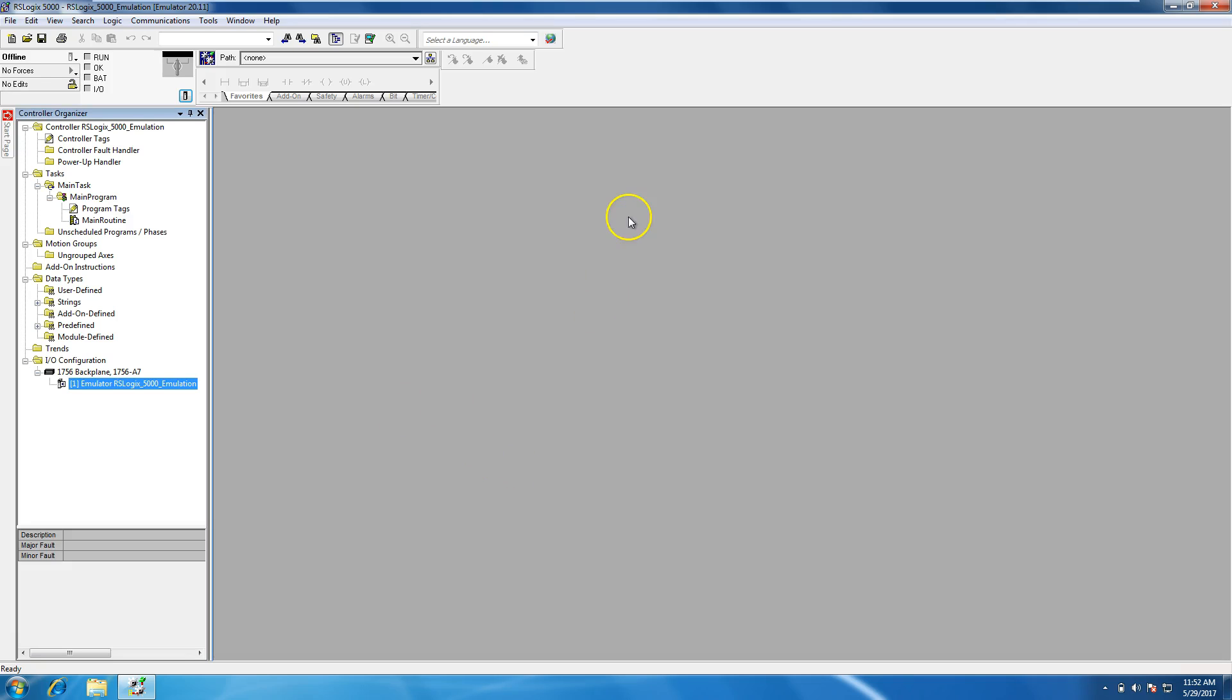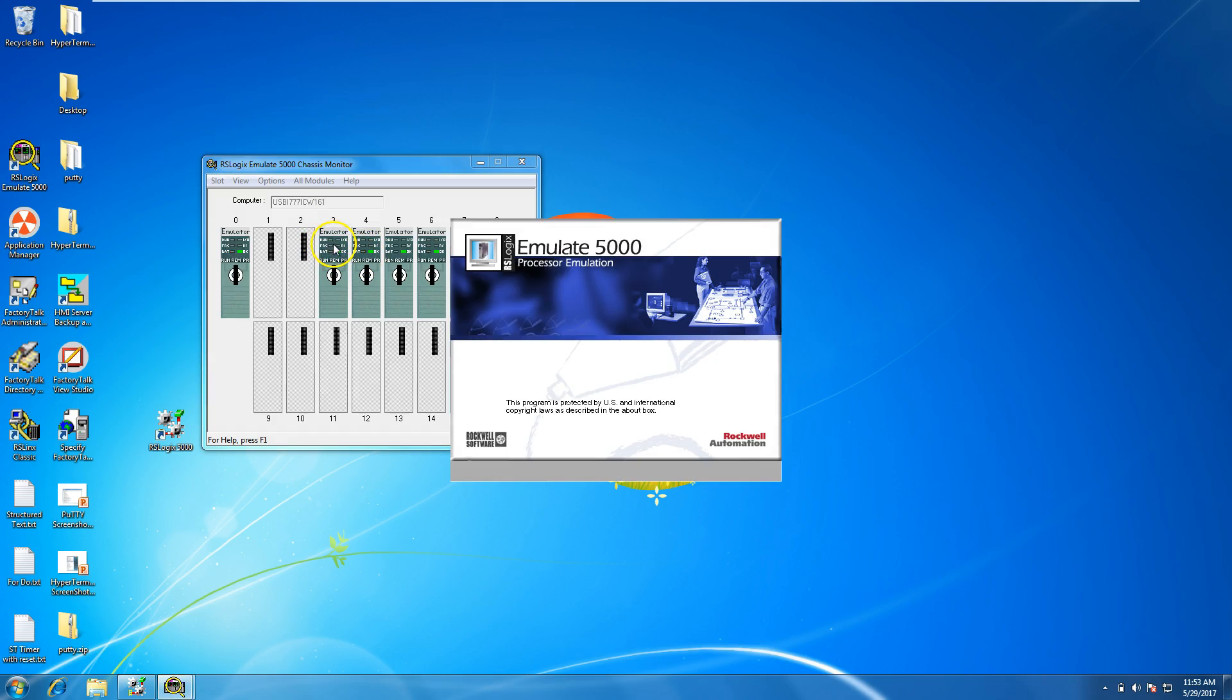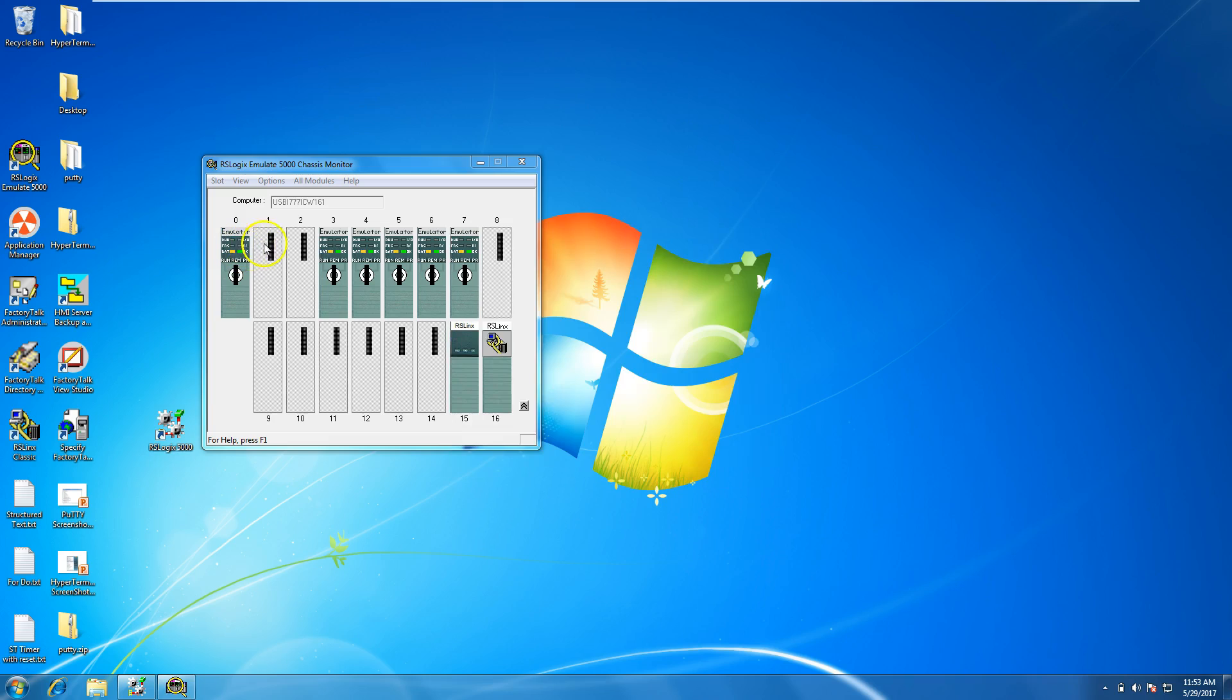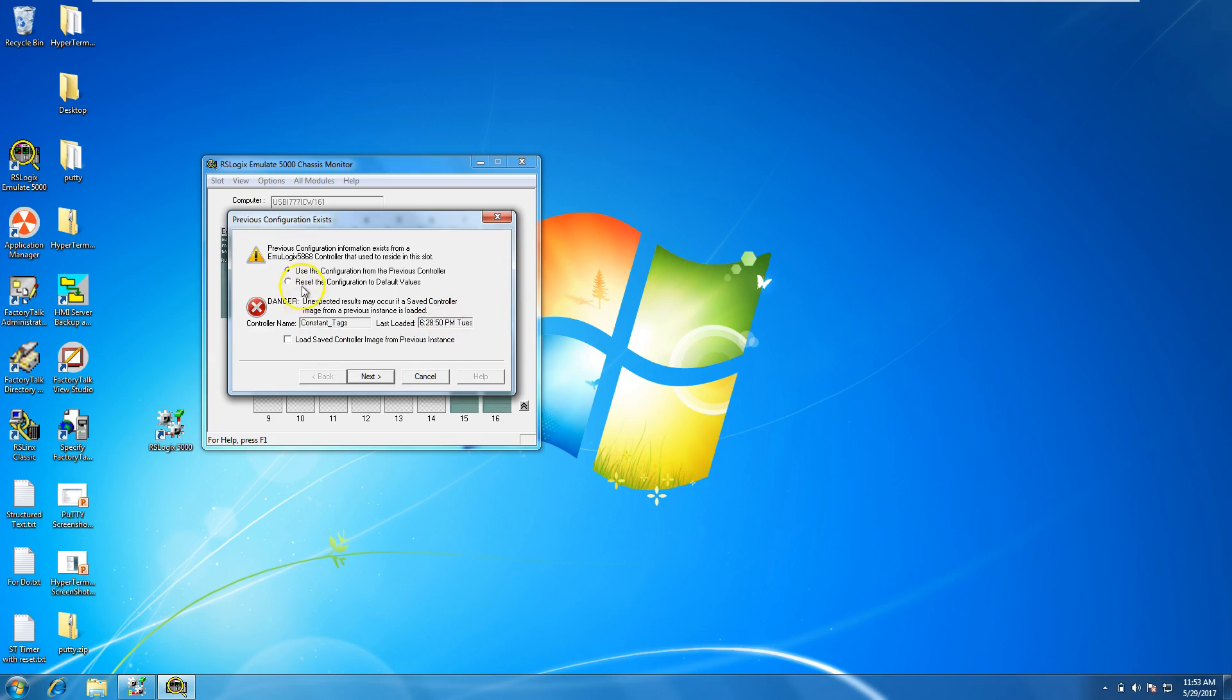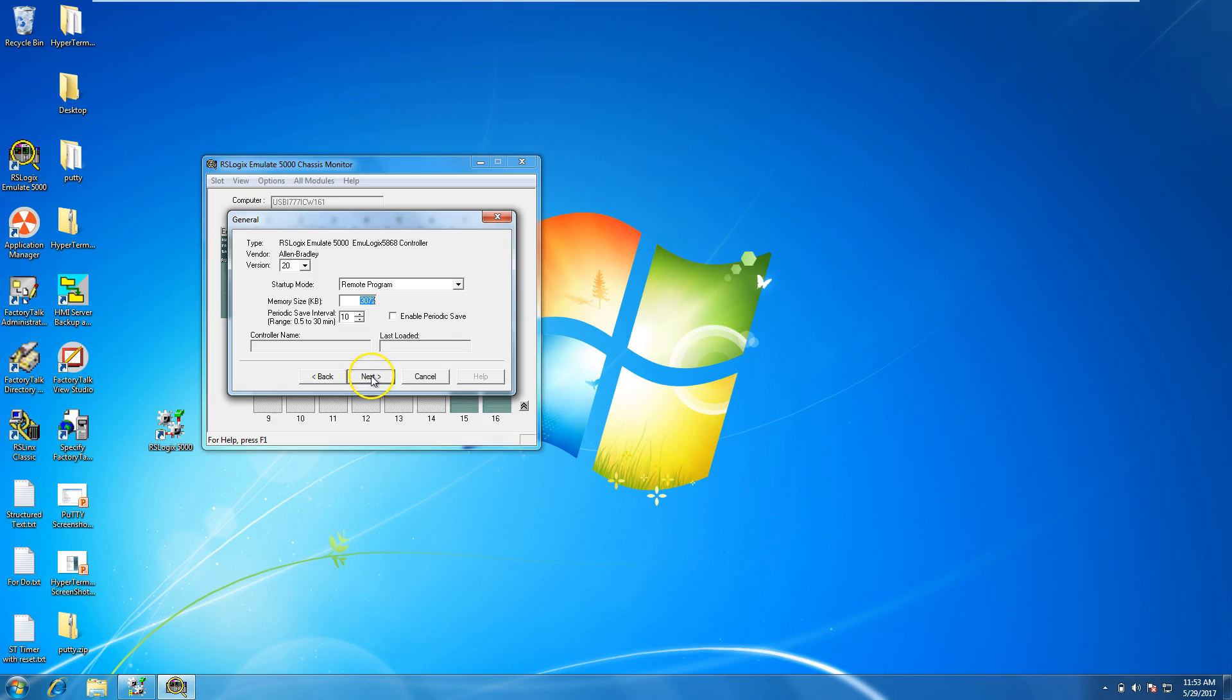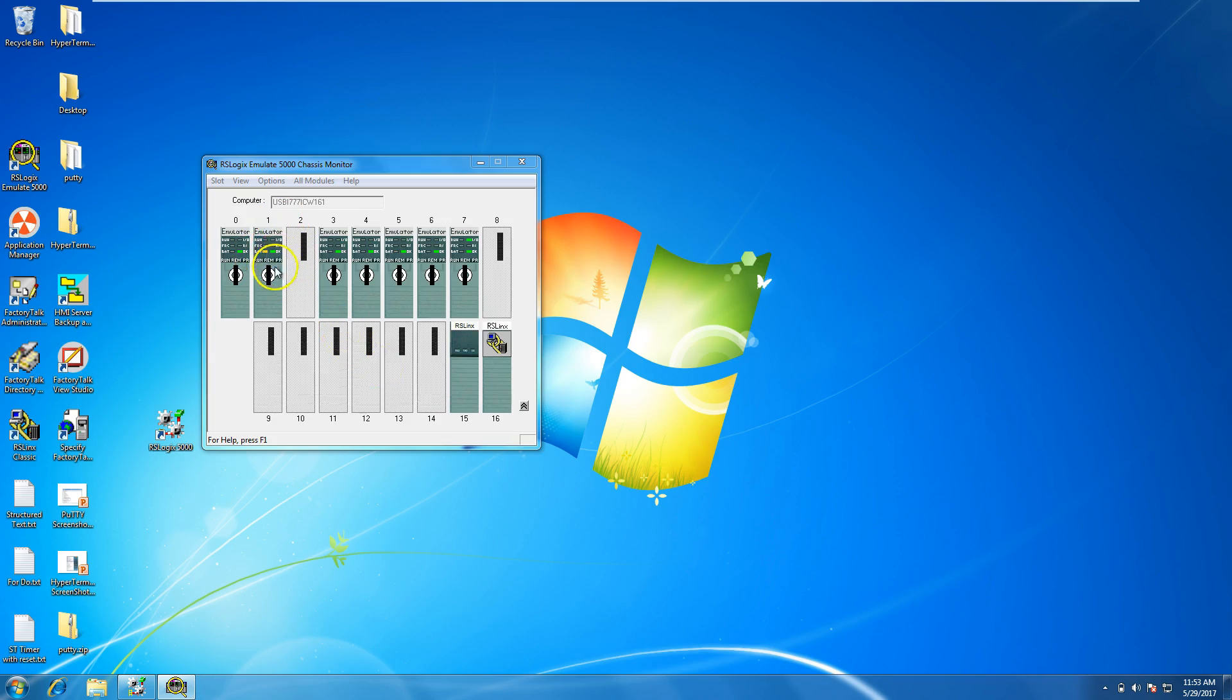Then we'll come back and we will open up the emulation. So now in the RSLogix emulate software, the emulation 5000, we're going to put a processor in slot 1. You can change the memory size if you want to. So if you have a big program you're doing, you can change the memory size. It depends on really your PC and what your PC can take. But when you're emulating something, you definitely want to look at your processor memory size. But for this instance, we're going to use default. And for most cases, you will use default.